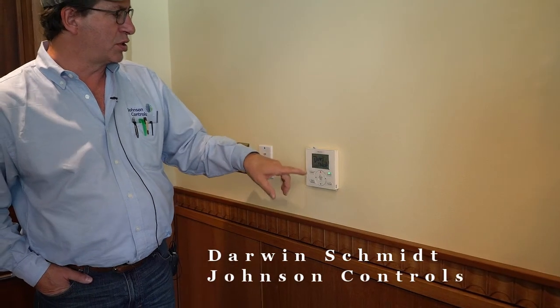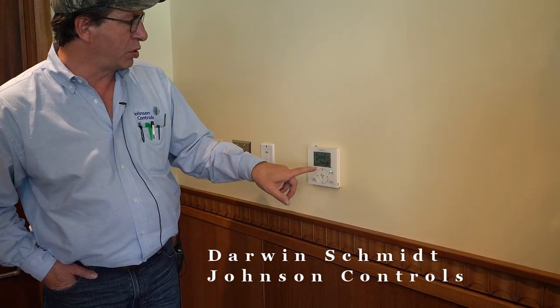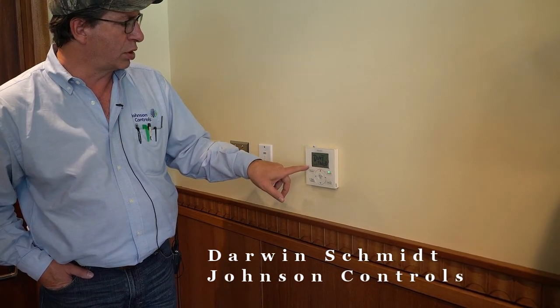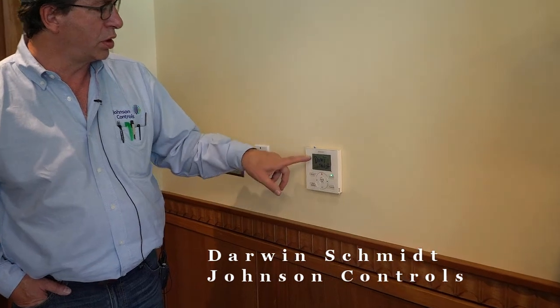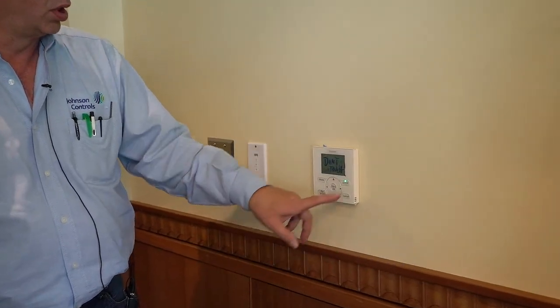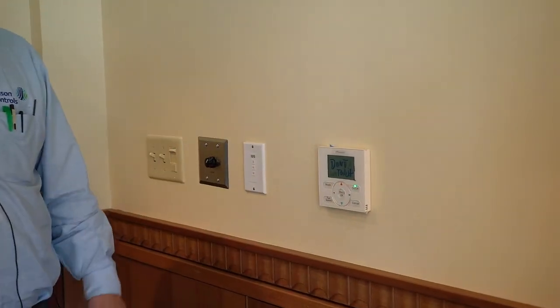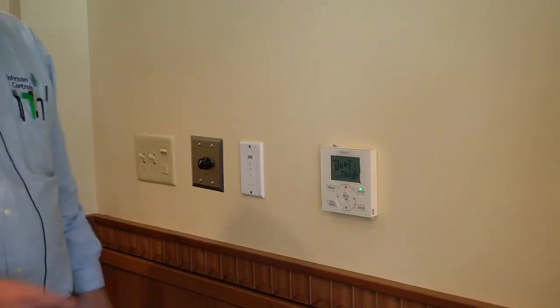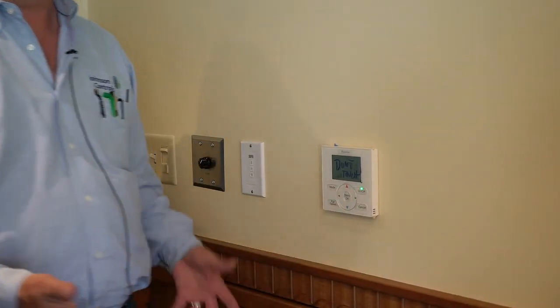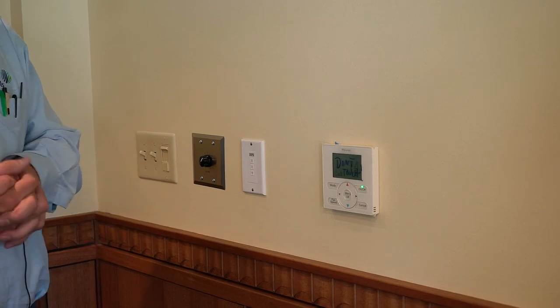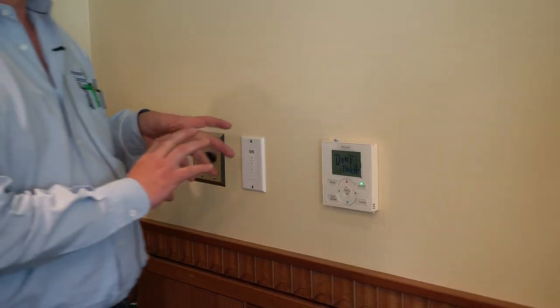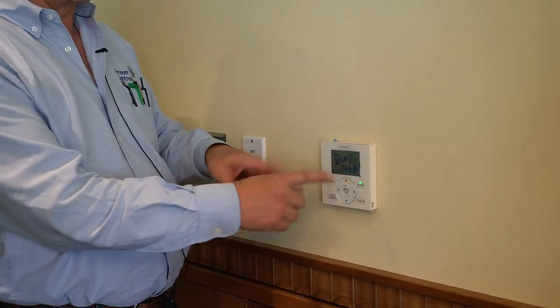So this is a digital display. It tells you your room temperature. It'll tell you your set point over here, your fan speed here, and whether you're in heating or cooling mode. It does have a manual on-off switch. If they don't have these locked out, anybody can come by and push that and it'll either turn it on or off. So that's something you might want to look at, is maybe getting these locked out. There's a way to go in here and program them out.